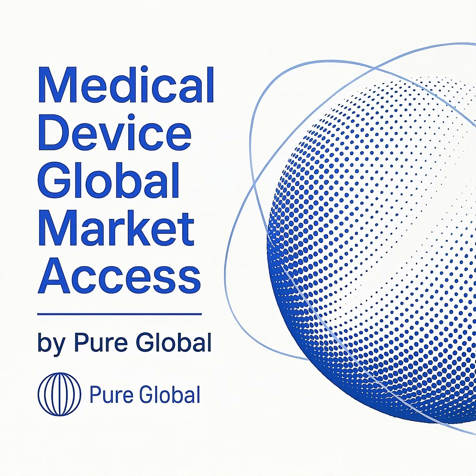The core purpose of an IDE is to encourage the development of new and useful devices while ensuring the protection of public health and safety during the clinical trial phase. Under an approved IDE, a device is exempt from several key regulatory requirements that apply to commercially distributed products. These include pre-market approval, PMA, pre-market notification 510(k), and establishment registration and listing. While manufacturers are also exempt from most quality system regulations, they must still comply with the design controls portion, as outlined in 21 CFR 820.30.